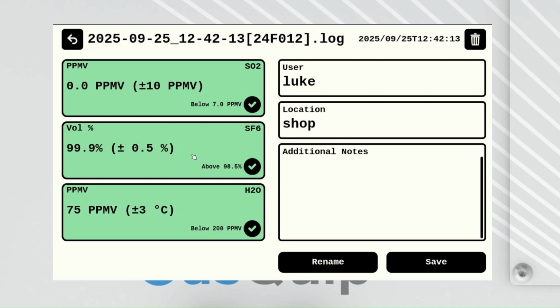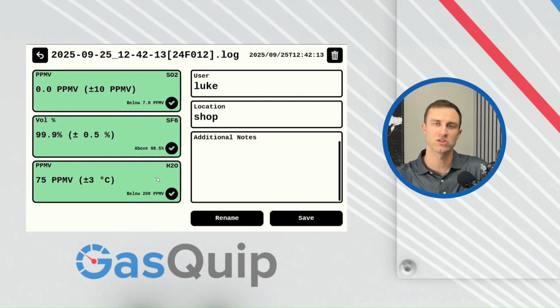Same thing for SF6, our test limit was set to 98.5%. So our actual reading was 99.9%. Therefore, we are above our test limit threshold, and our sensor readout here turned green. Same thing for H2O. We're below 200 ppmv, and our readout read 75 ppmv. So the whole thing turned green and is a check mark. Test limits are meant to just be a reference for the user to determine whether or not that test that they ran met the criteria, whatever the criteria may be, that they need to see.